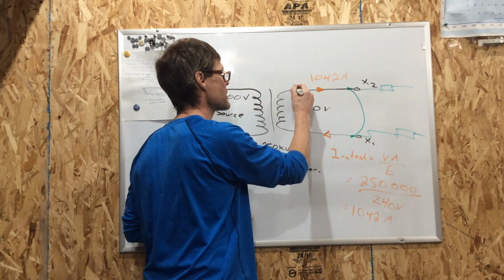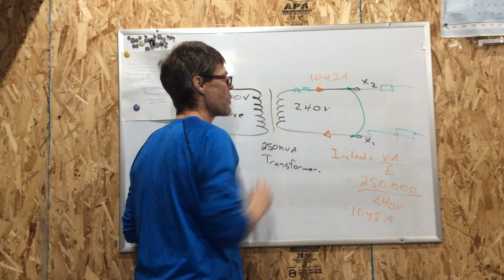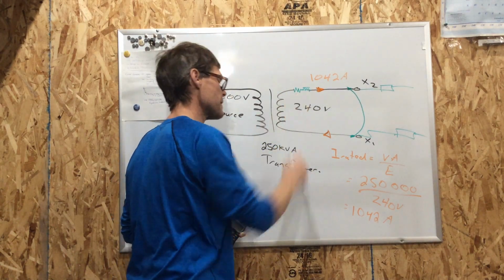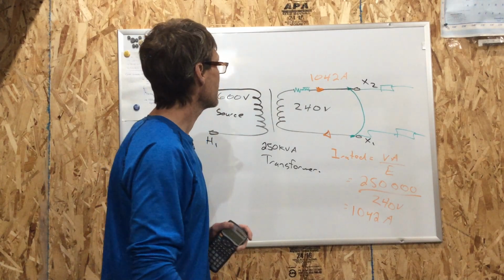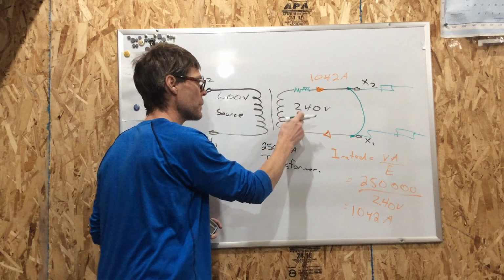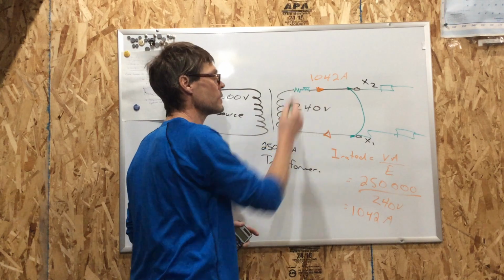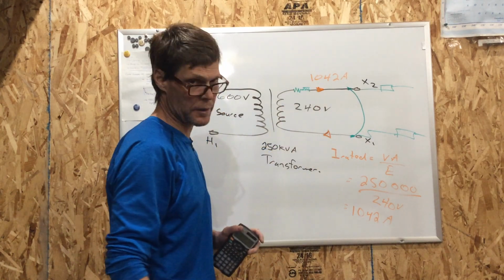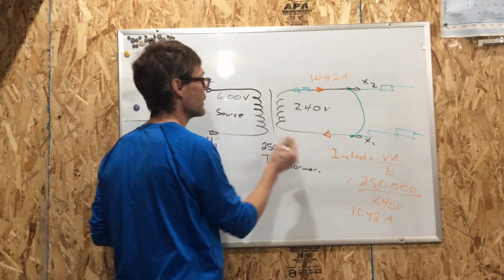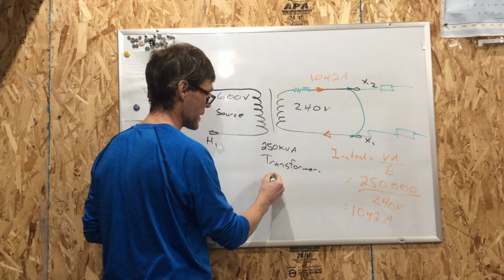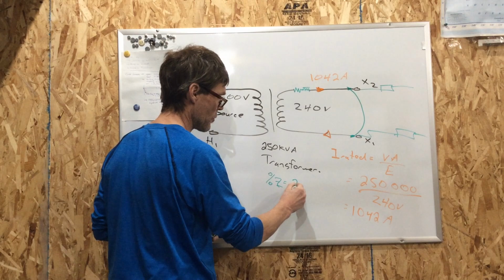Well, the internal resistance and the XL of this winding. Well, think about the size of this transformer. There's not going to be a whole lot of resistance in those windings. So, what we have stamped on these is something called percent impedance. That takes into account this right here, and we'll talk about how we get percent impedance. Percent impedance comes from our short circuit current test.